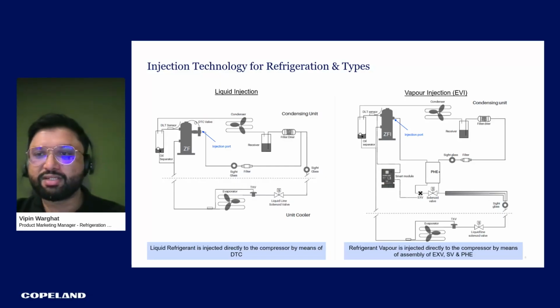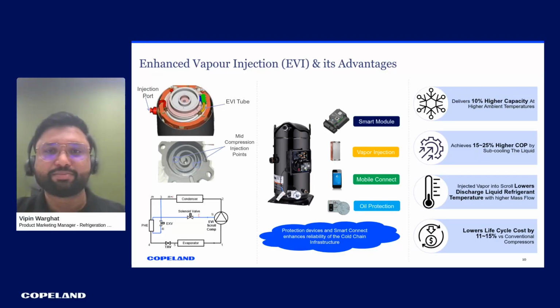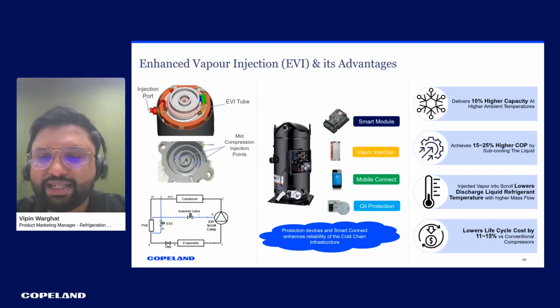If you could move to the next one. Like I mentioned, the vapor is injected inside the scroll, and if you see here on the screen, there are ports available at the mid compression, which is where the vapor is injected into the vapor injected scroll. With this, we are subcooling the entire scroll in order to achieve higher efficiency, which is 10% higher efficiency at similar conditions, and thus also improving the efficiency to 15 to 25%. And in turn, this improves the life cycle cost by 11 to 15%.